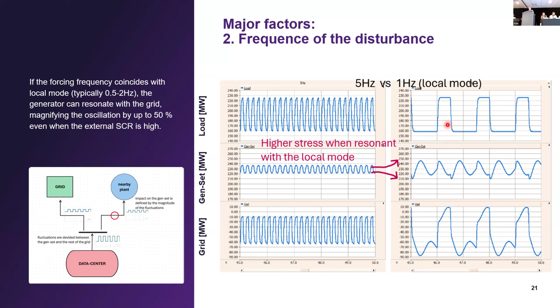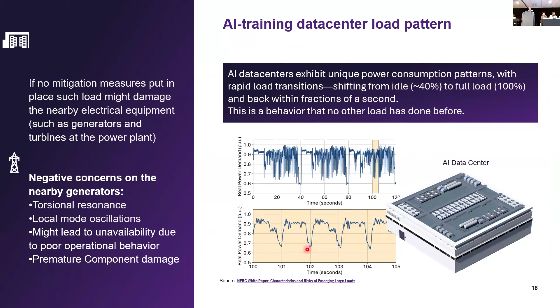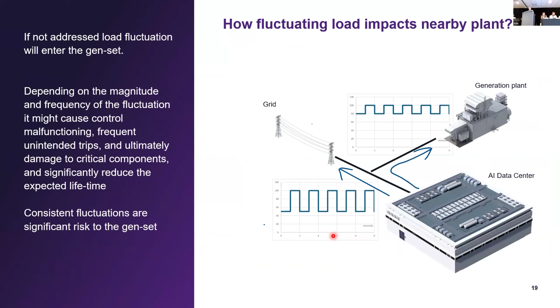If I go back to this graph published by NERC, what we see here is a big dip exactly every second. So there is a huge 1 Hertz component already. This is factor number two, and factor number three is the ramp of the change. Amin mentioned this: we are talking about millisecond changes on a scale of megawatts, and the ramp plays a huge role in the stress the machine experiences.